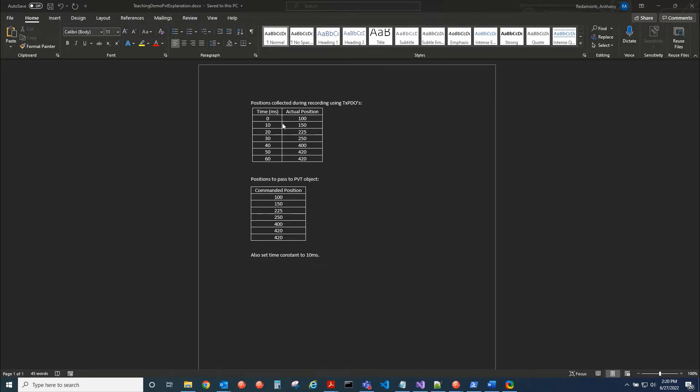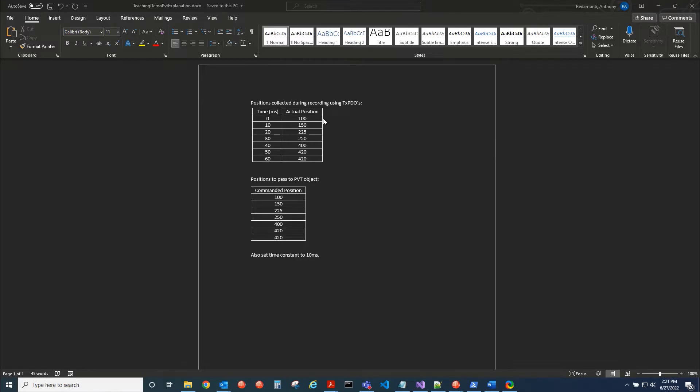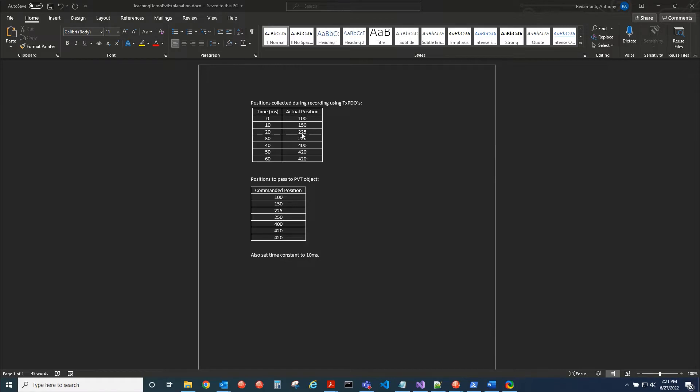Here's a kind of visual interpretation. So we're going to be collecting positions over time using TPDOs. So we're going to set the sync pulse to 10 milliseconds, meaning that every 10 milliseconds some TPDOs will be transmitted by the drive back to us, giving the position. So we're going to get the actual position, a hundred counts, 150 counts, and then all these different positions on all the axes.